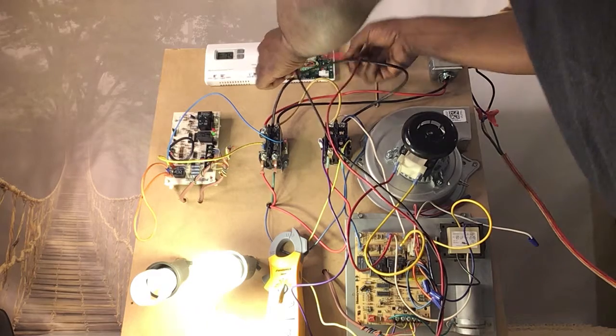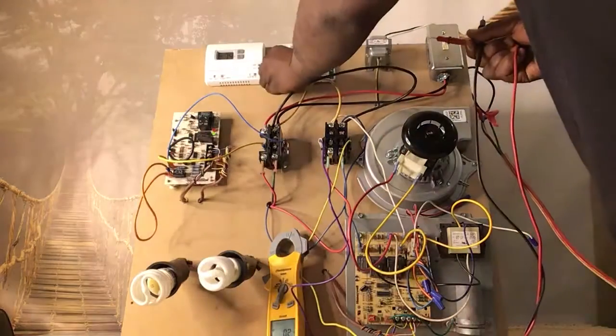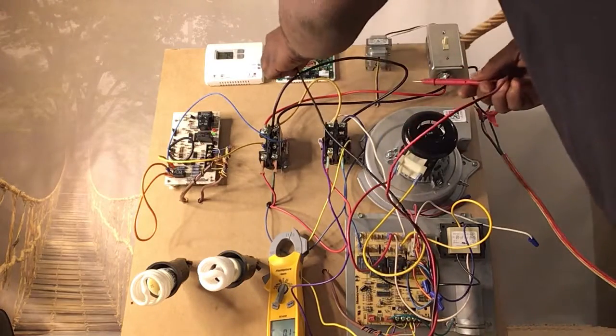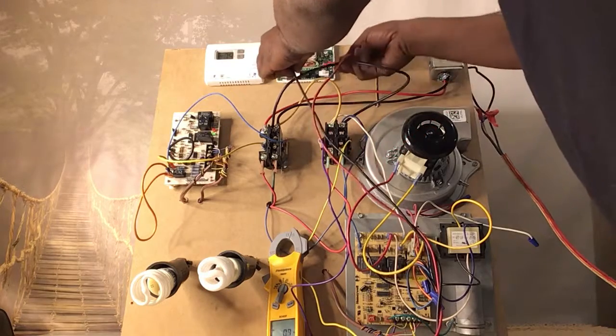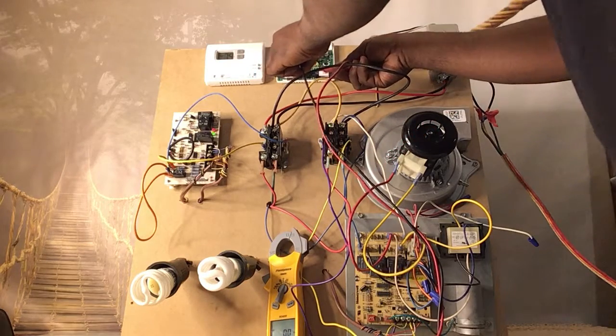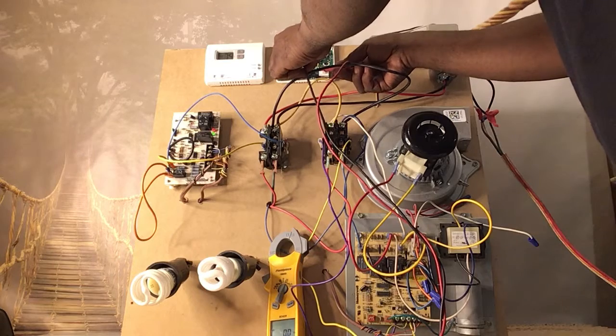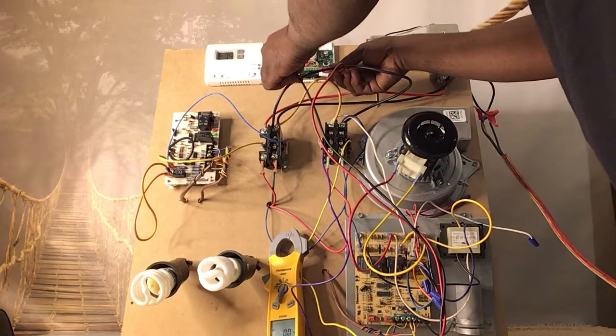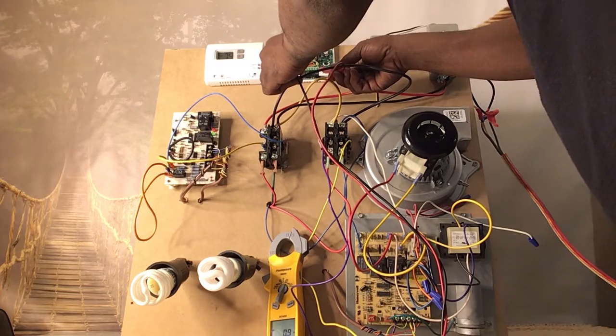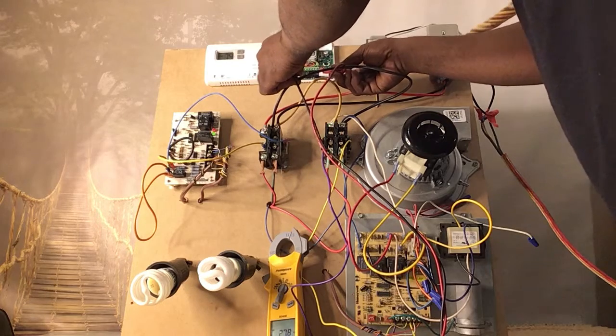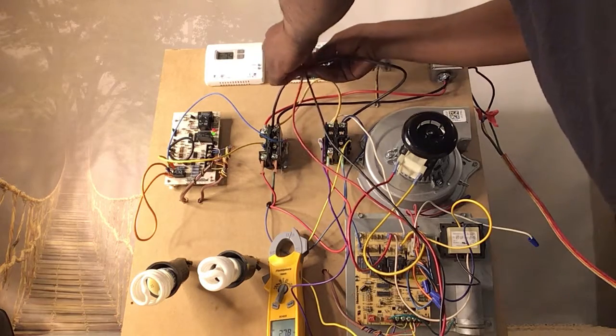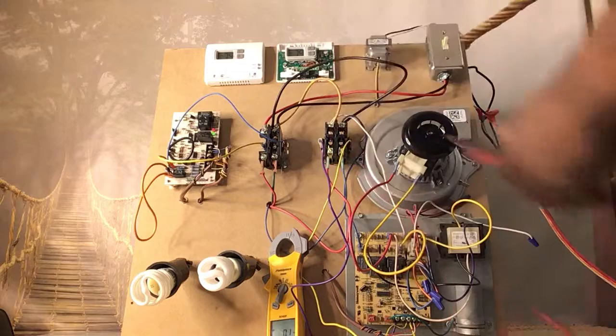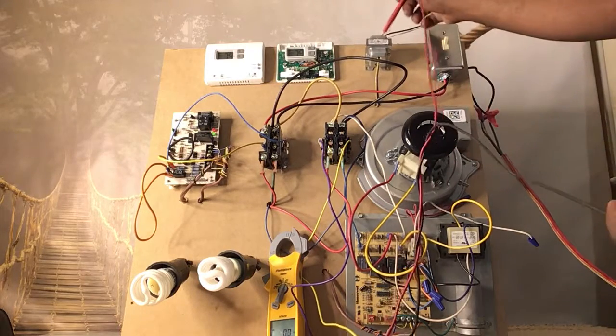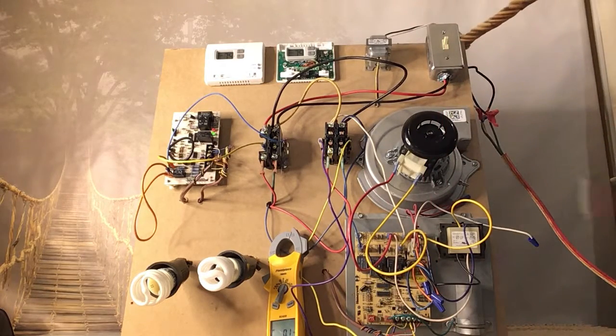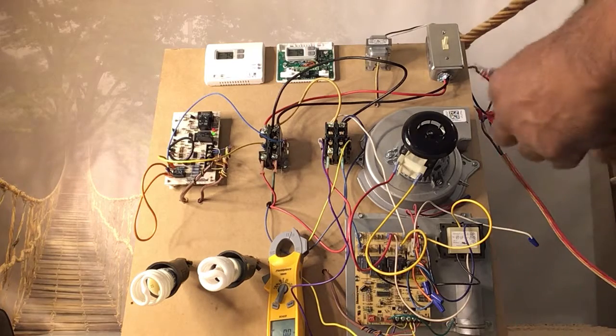If we shut it down, put it in the off position, and go from common to yellow again, 0 volts. No voltage. I don't know if y'all can see that or not, but 0 voltage. So now if I take off the common and go to the red, I know that I have an active 24 volts still. That also lets me know that my transformer is still good because I have 24 volts. If I didn't have 24 volts, then I would go backwards to this.